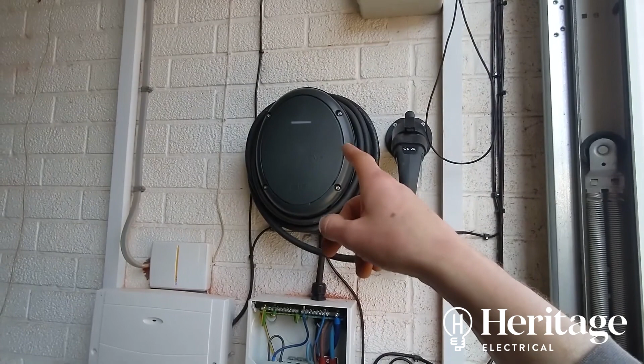So we've just done a measurement of ZE, where we disconnect the earth, clamp around that, one crocodile clip around that, and then probe onto the line. So that's given us 0.34.